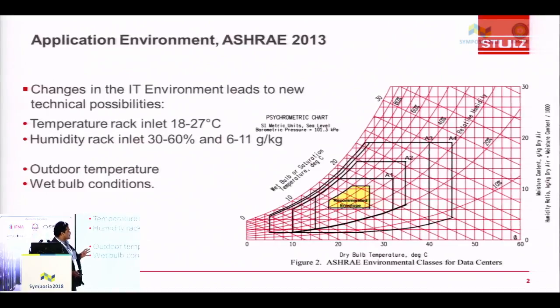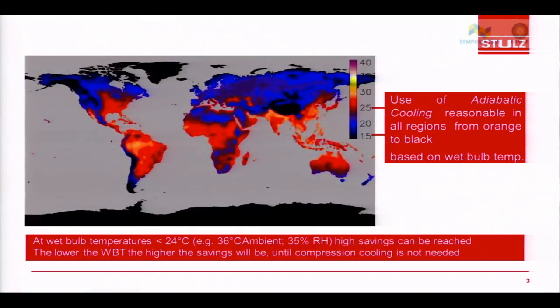So this ASHRAE is also certified. Again, there is a recommended envelope which says maintain the temperature inlet from 18 to 27 degrees Celsius. Here is, I hope, the global map. So we all have to use free cooling and adiabatic cooling now to ensure that partial PUE is improved in the data centers. Fortunately, India falls in an adiabatic range, where you can see the use of adiabatic cooling is reasonable in all regions from orange to black.